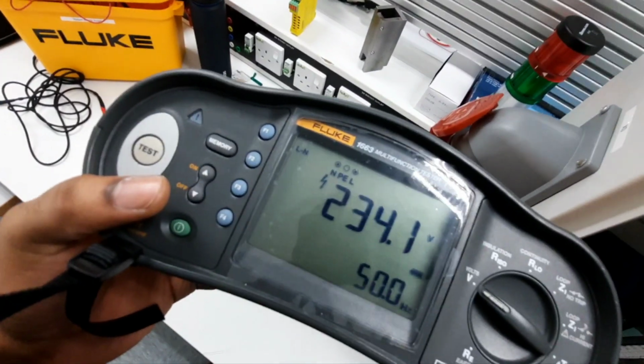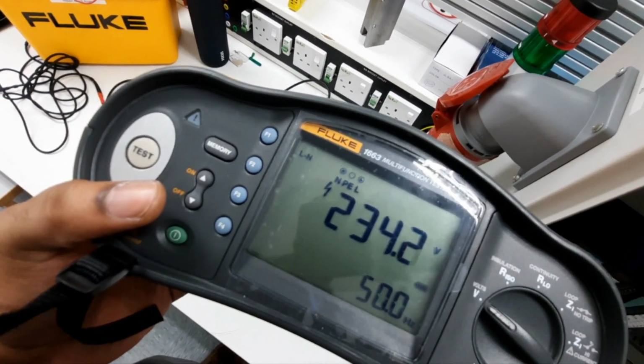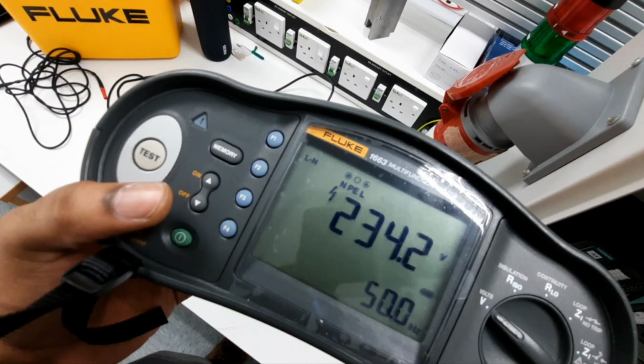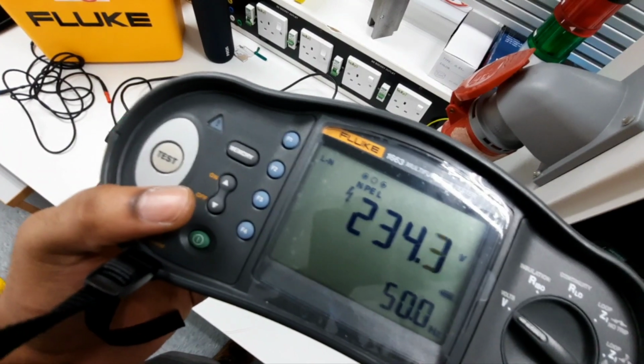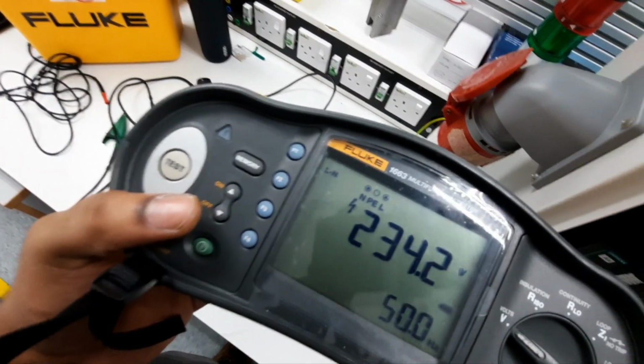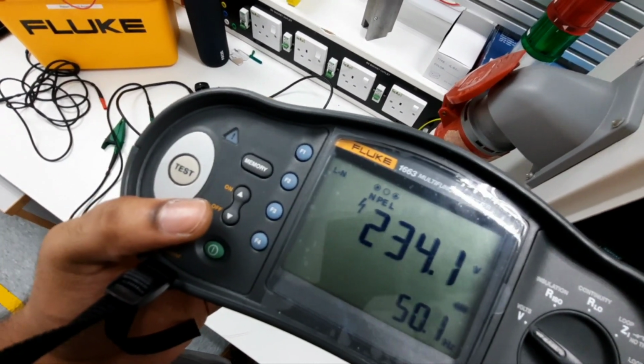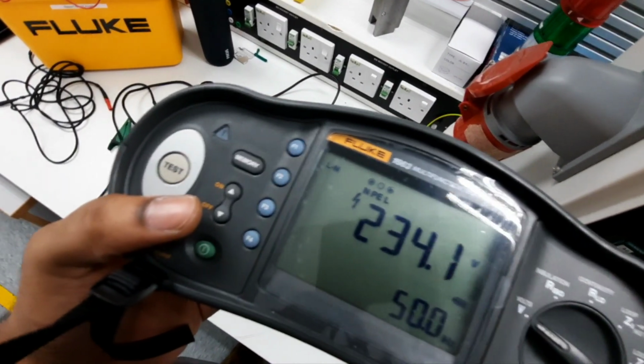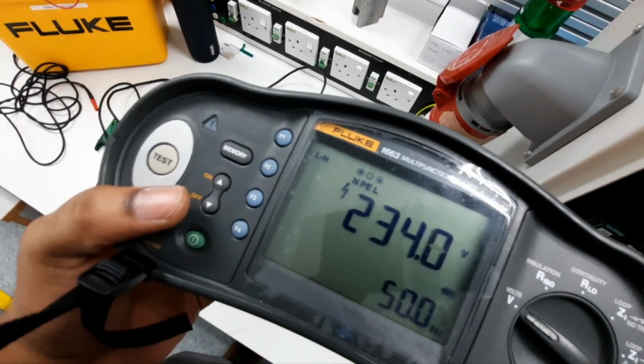So this is not the contact voltage, this is actually the line voltage for a single phase. So it's around 234, in the range, but must be around 230. So with this one, it's already good, this is okay already.